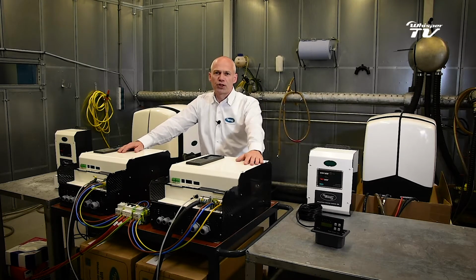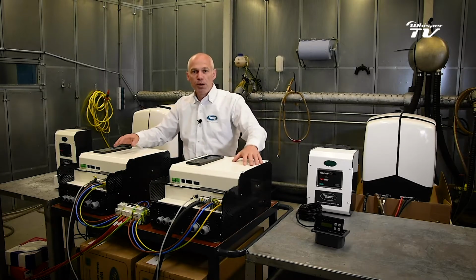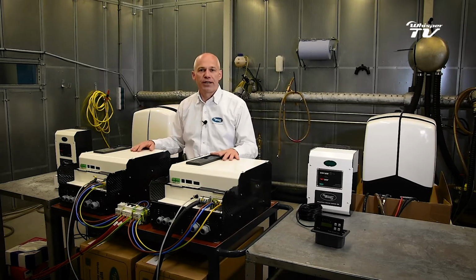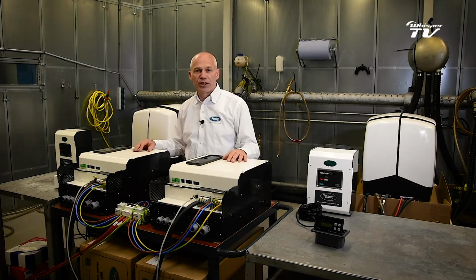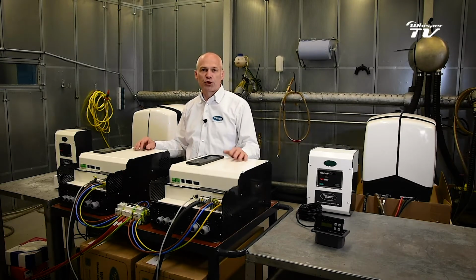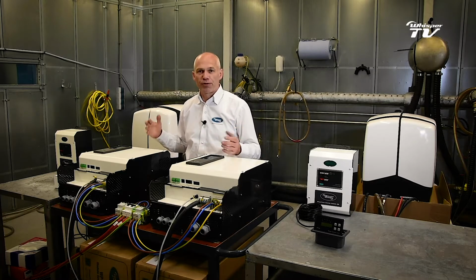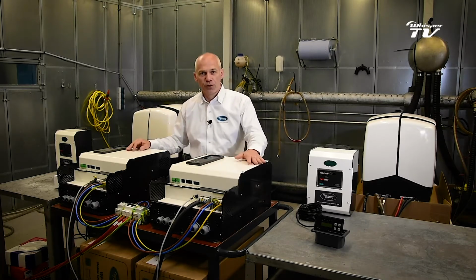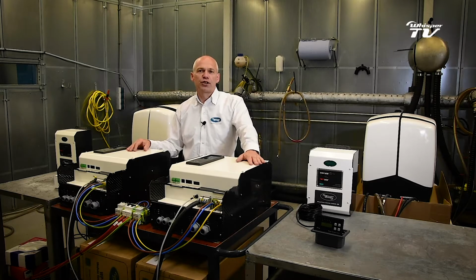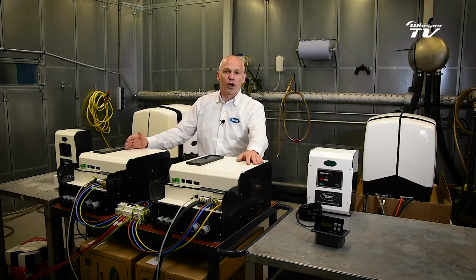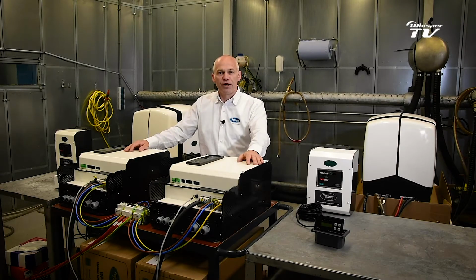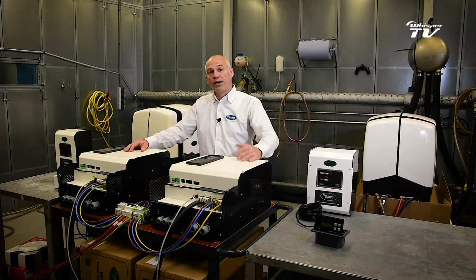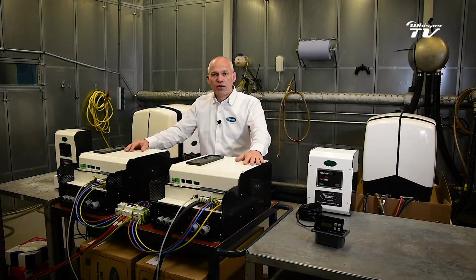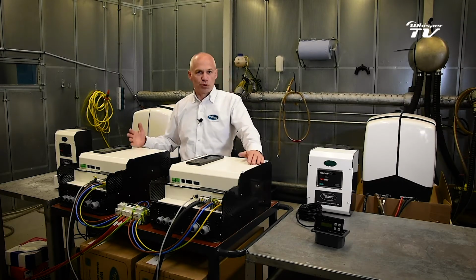By installing two units, the electrical load on the Genverters will be balanced much better than when a large generator is installed. In case of a 50% electrical load, the engine of large generators will throw out soot, and that's not very environmentally friendly. The audible noise level of these generators is extremely low and substantially lower than a traditional 1500 or 1800 RPM 30 kVA generator. In general, those generators are oversized, and so we really measure a low dBA. Vibration of the units is negligible.